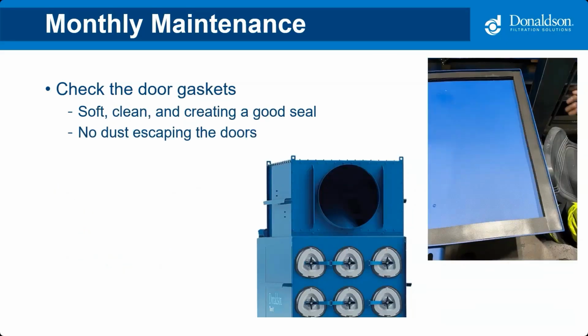And then last, you also want to check the door gaskets. So as you're opening these doors to inspect these large collectors, there's a picture there on the right that shows a good condition door gasket. That's a brand new one from our factory. You just want to make sure they're still soft, pliable, they're still sealing well, and if not, you need to replace that gasket when you put the door back on.